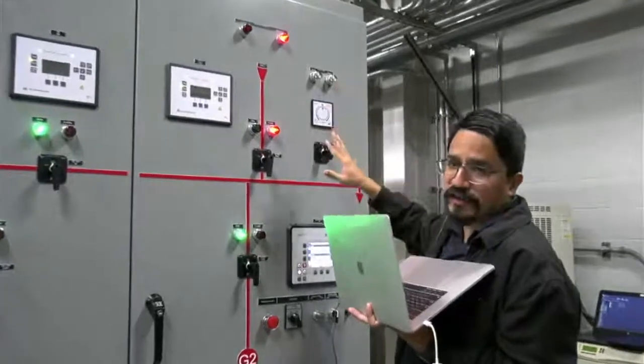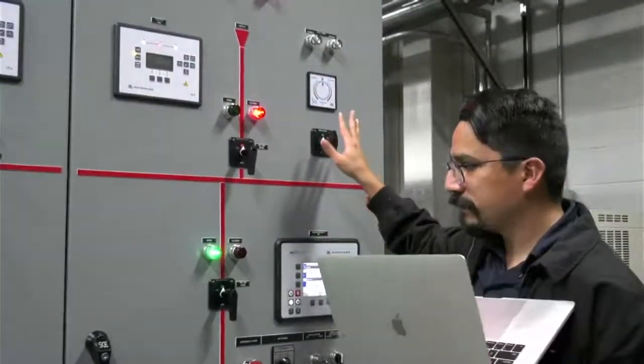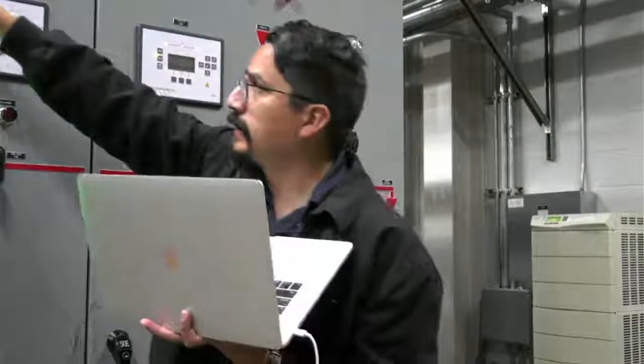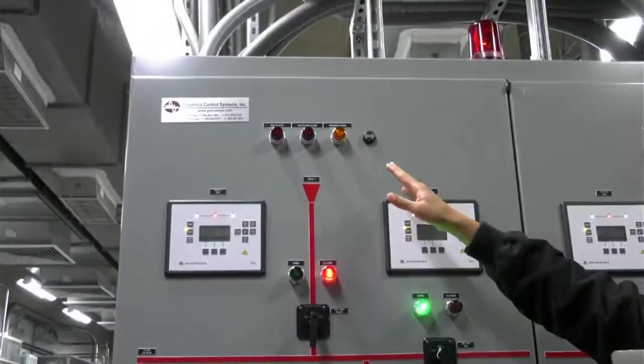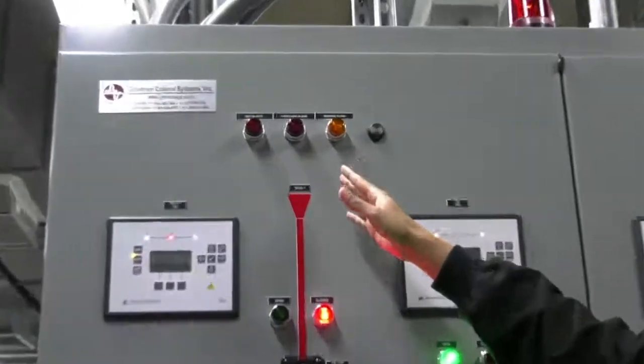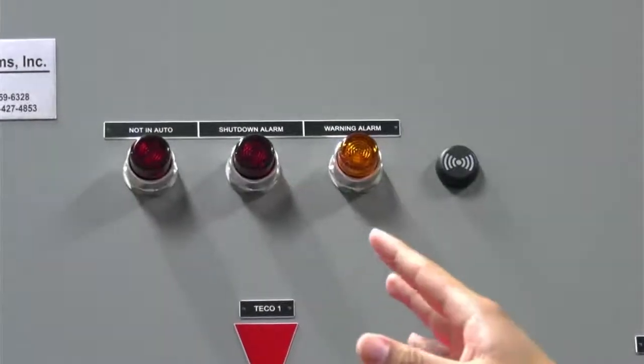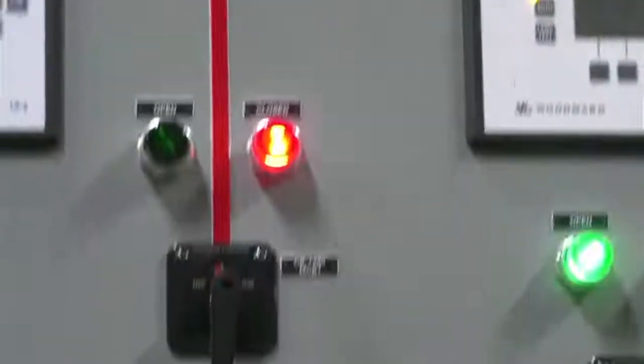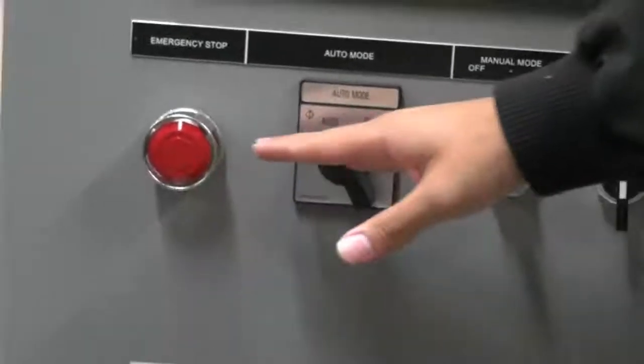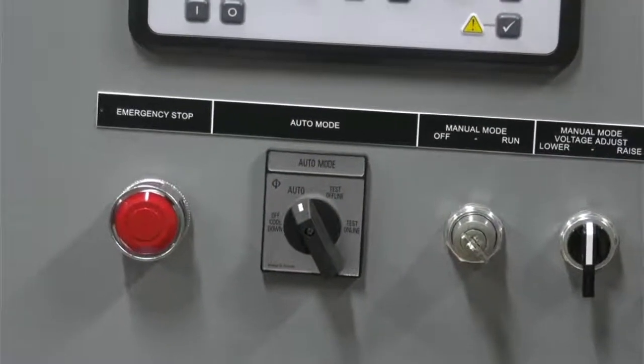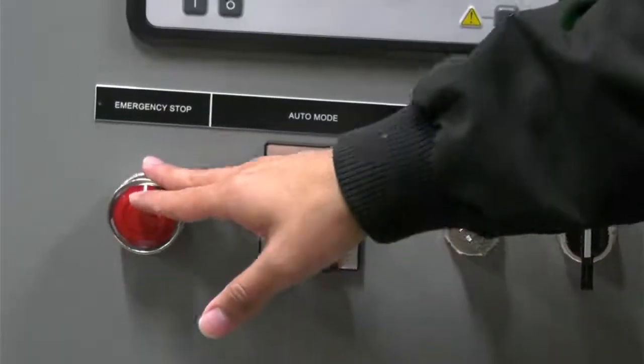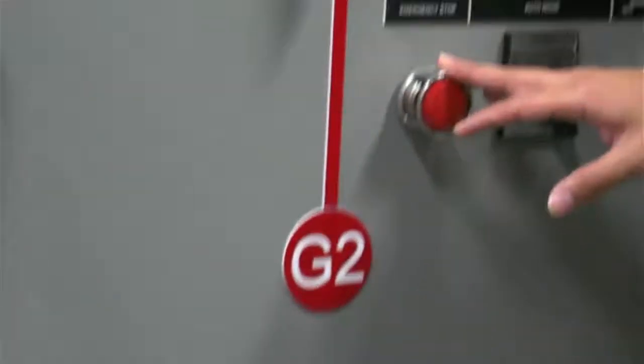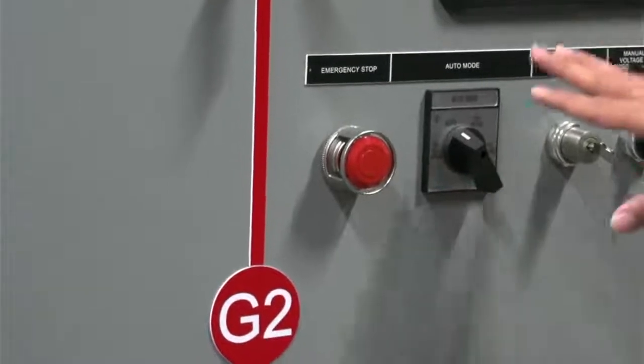Over here we have a unit to synchronize the system manually. We have some pilot lights on the top indicating status, warning alarms, shutdown alarms, and when the system is not in auto. On the bottom, this row is for manual control. We have the emergency e-stops, two of them, one for G1 and the other for G2. They are based on the same layout, so this part over here is the same for each generator.